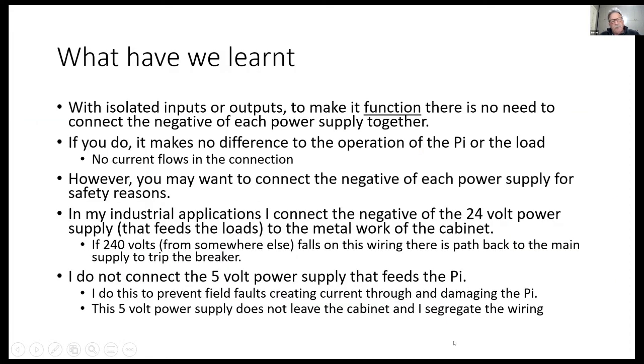So I quite often connect the negative of the 24 volt power supply that feeds the loads to the metalwork of the cabinet, but it's for safety, not for function.